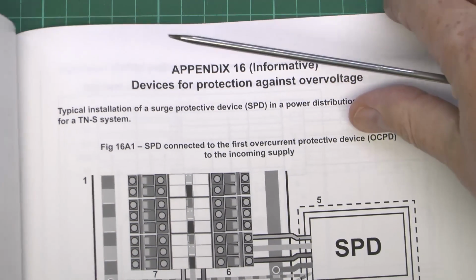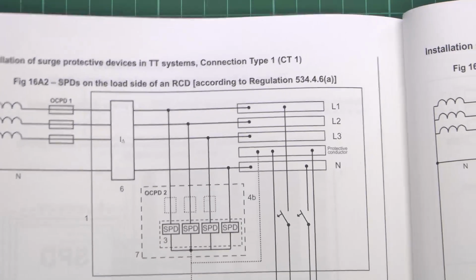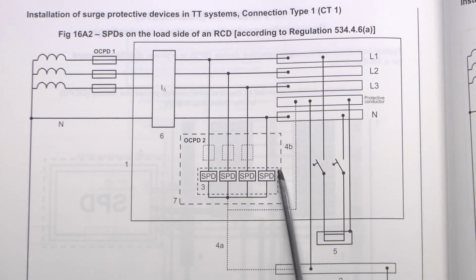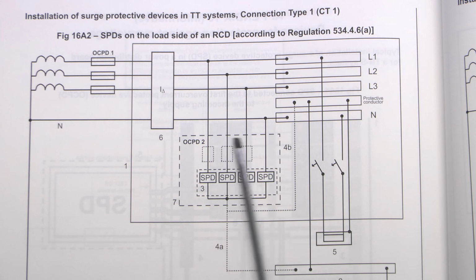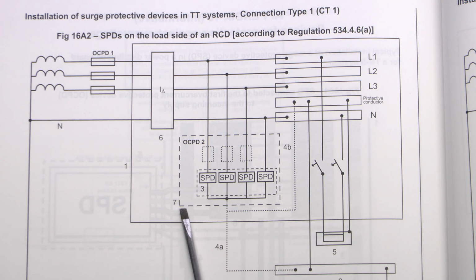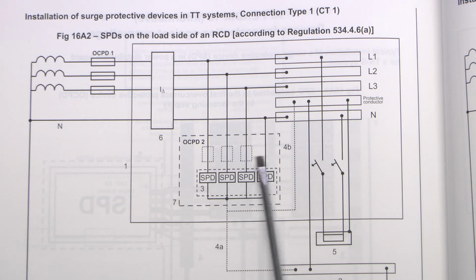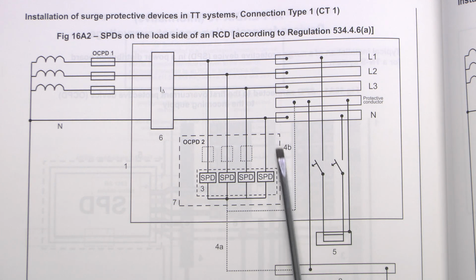There's a minor change to the diagrams on these pages and following pages. The difference is we've now got a box referred to as 7, listed as an SPD assembly, and what we've now got is overcurrent protective devices shown within the assembly for the surge protective devices.